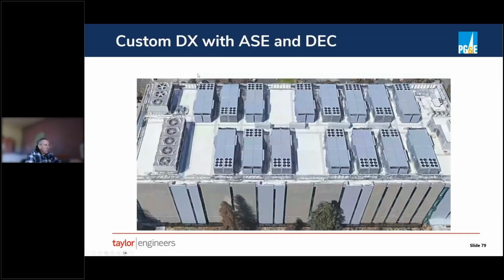Okay. Similar to that other roof shot we showed, these are rooftop units that have air economizing and direct evap, but they're custom units. One of the big advantages there is the ability to configure the intake and exhaust to try to minimize reentrainment. So in this case, the exhaust is basically shot up in the air to keep it away from the intakes on the side. And we had more flexibility on control sequences to deal with the goofy stuff we were seeing on compressor staging and minimum runtime. So it had a lot of the advantages of efficiency and redundancy, and addressed some of those disadvantages.